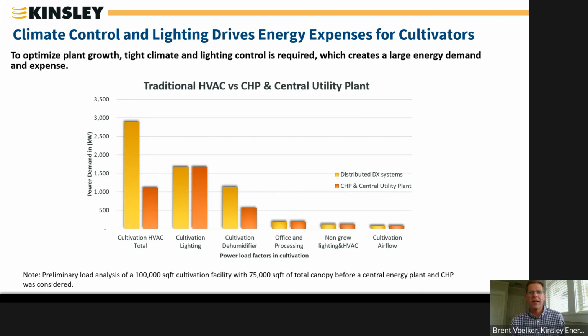Yes. Generally, the CHP units are designed for 24/7 operation, so they're more durable and higher efficiency, consuming less fuel and requiring less service compared to a more standard, typical standby generator running in what we call prime power mode. So there's a bit more capital cost up front for combined heat and power, but it's recovered through higher efficiency and lower cost of service.